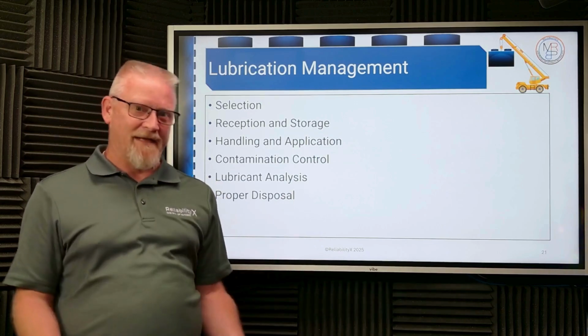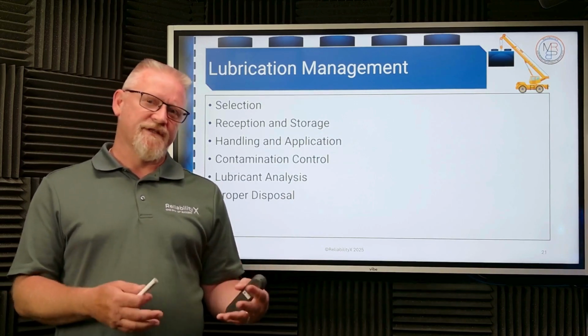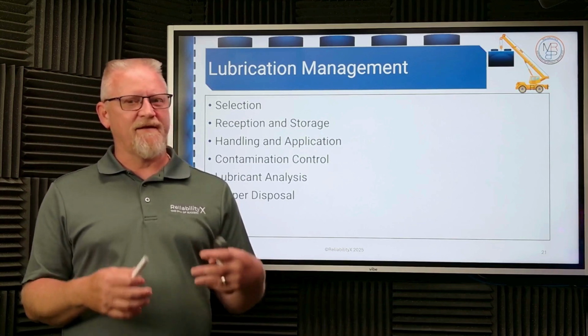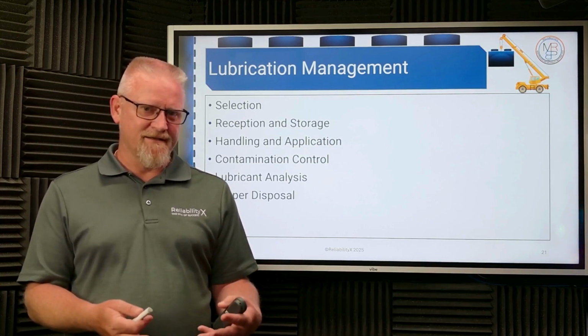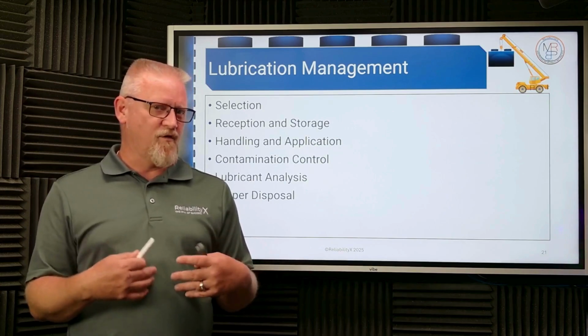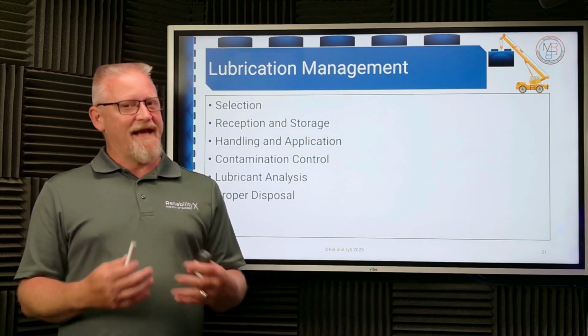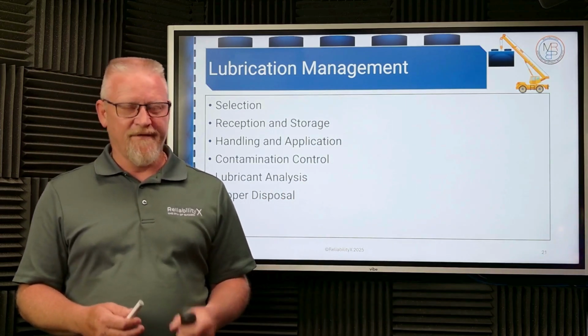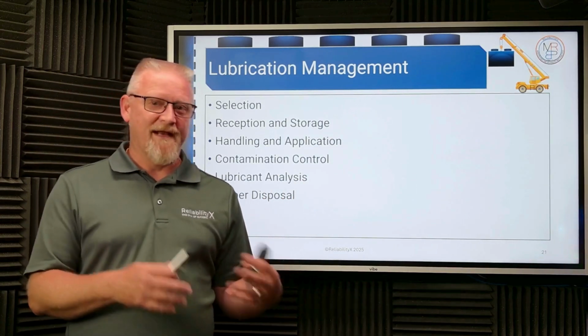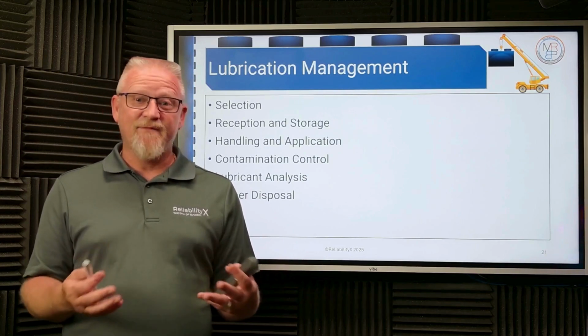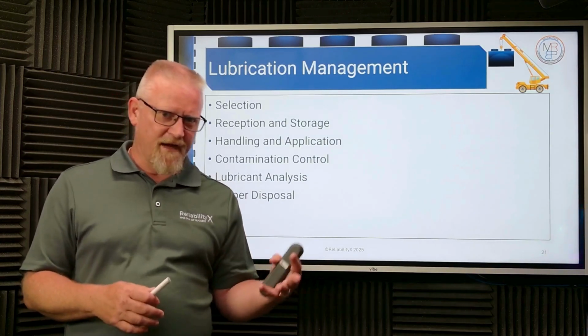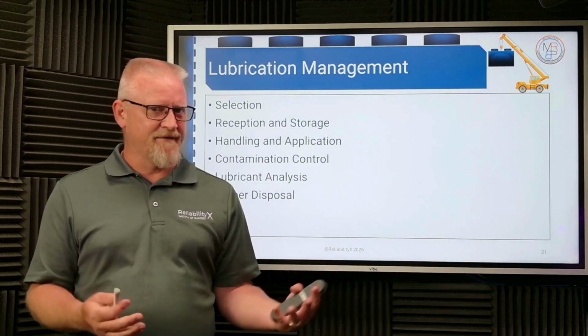What does that mean? Well, an ISO standard against lubricants ensures that the particle counts and sizes are adequate for the equipment you have. When you buy new lubricants, they have an ISO standard listed on them. And your equipment has specific tolerances in between things like roller elements and the inner and outer race of a bearing.